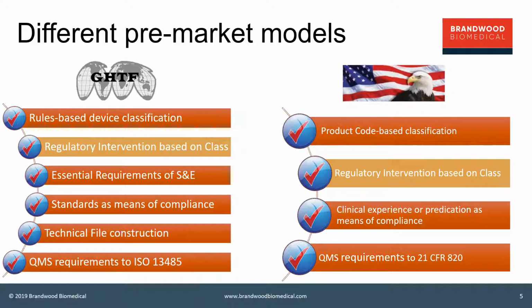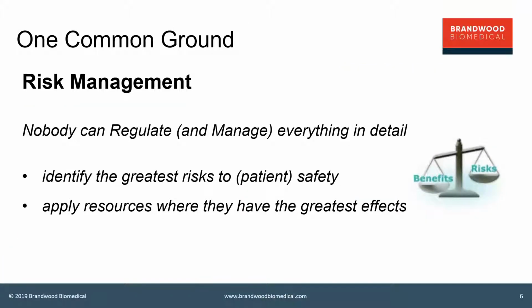Obviously, quality management system requirements also differ. In the GHTF framework, 13485 is the standard for application, whereas in the USA, currently FDA operates under 21 CFR 820. There is one big commonality, and that's obviously risk management. So essentially, nobody can regulate and manage everything in detail.